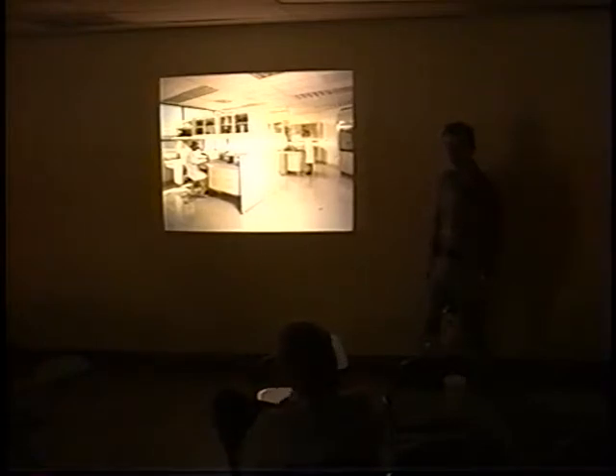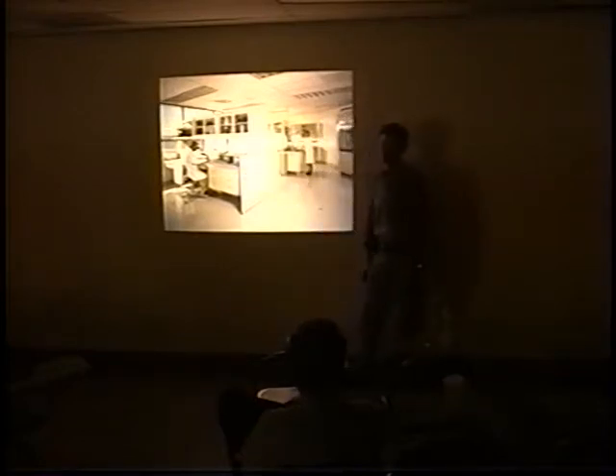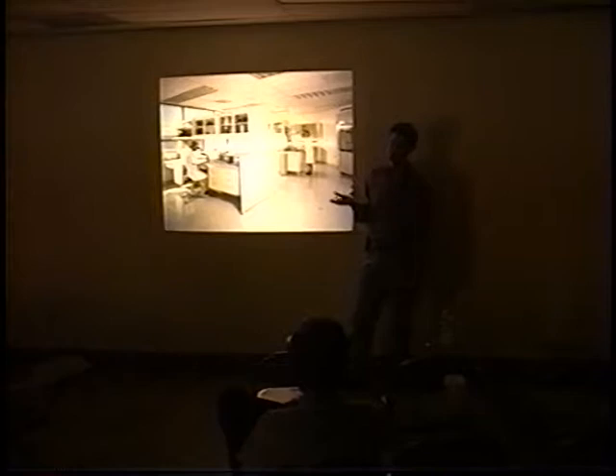Is there an importance to what colors you use inside the lab? On the lab benches themselves, unfortunately, you're really limited because of problems of staining and so forth. Only some colors can be used integral into the lab bench tops, because if you use something like an orange, it compromises the countertop, so it doesn't clean very well, and it's not resistant to things like acids or bases or whatever. For the ceilings and flooring materials, there's a little bit more leeway, but even there, there's a very limited amount because of maintenance.